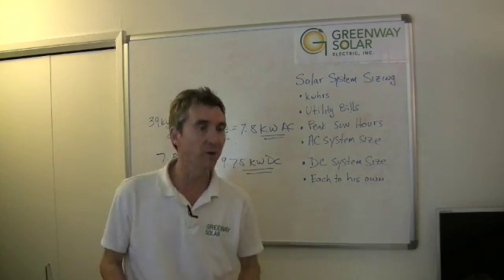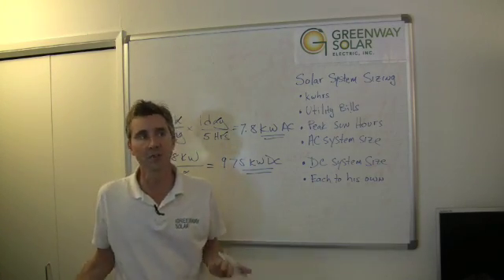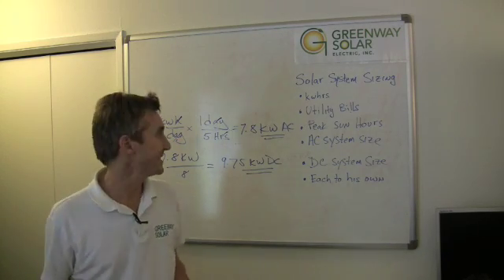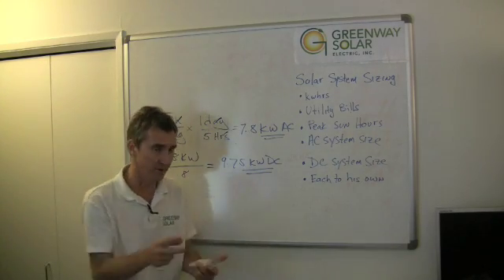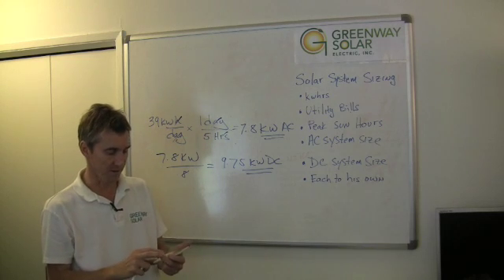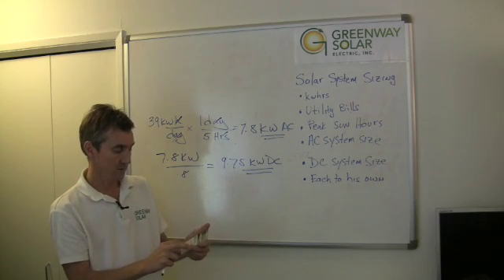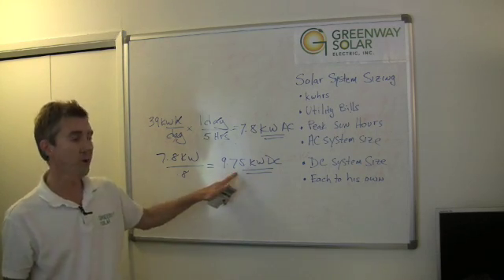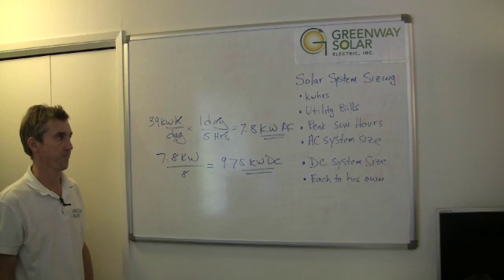Now when you go buy a solar panel, which we sell, they all state their DC power output. So we use a lot, for example, of Sharp 235 panels, which are 235 watts DC. So just for the heck of it, since I'm right here and doing this, why don't we say we have a system this size. How many panels would we require? Because that's kind of what you might be thinking. 9,750, 9,750 watts divided by 235, 41 panels. 41, 235-watt panels would give us a 9.75 kilowatt DC system.